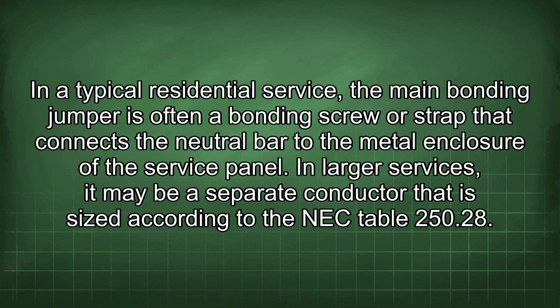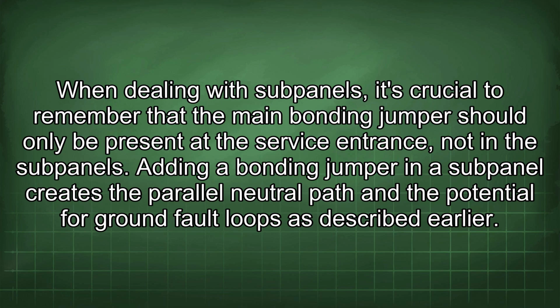In a typical residential service, the main bonding jumper is often a bonding screw or strap that connects the neutral bar to the metal enclosure of the service panel. In larger services, it may be a separate conductor that is sized according to the NEC table 250.28. When dealing with subpanels, it's crucial to remember that the main bonding jumper should only be present at the service entrance, not in the subpanels.